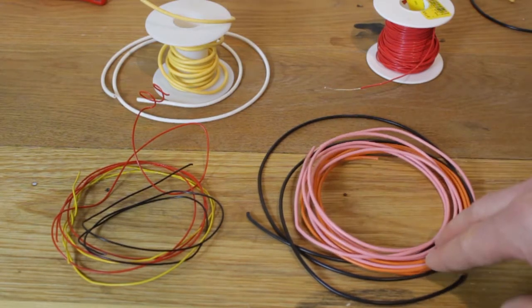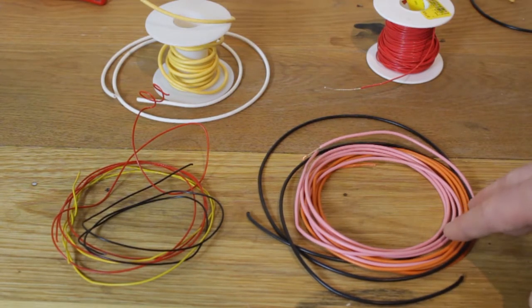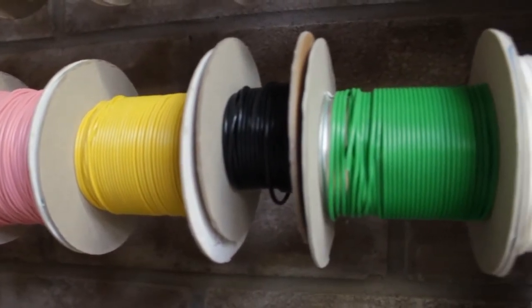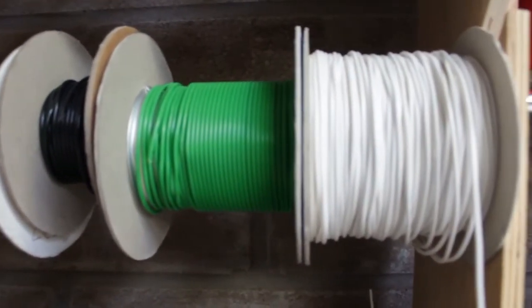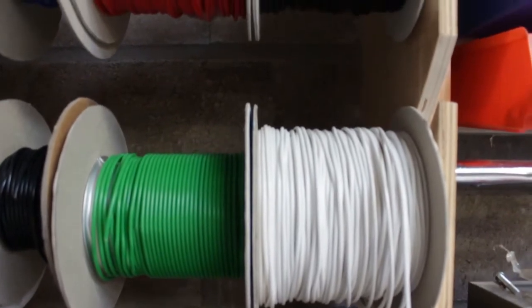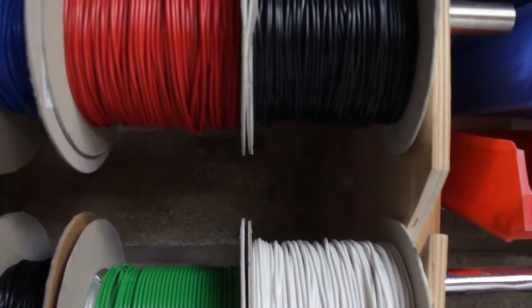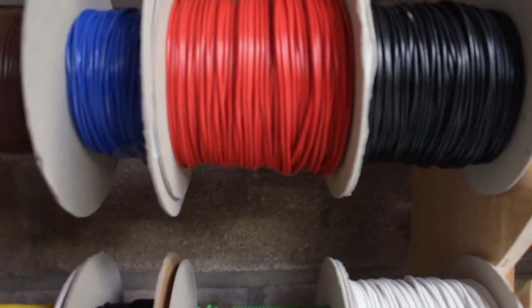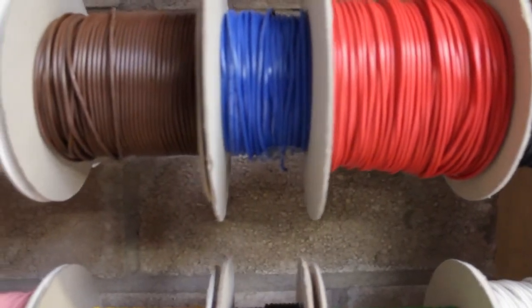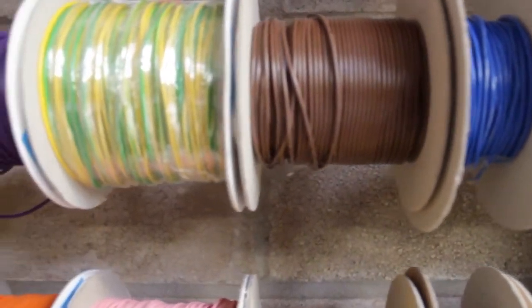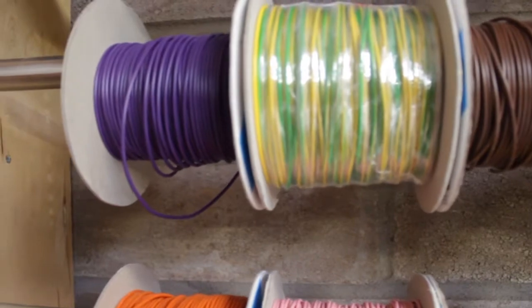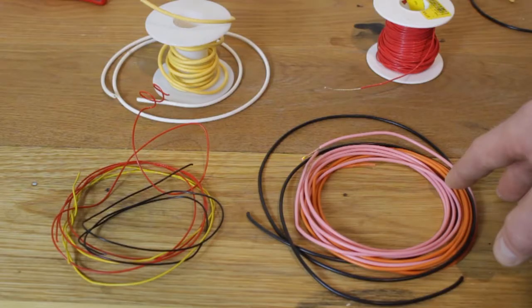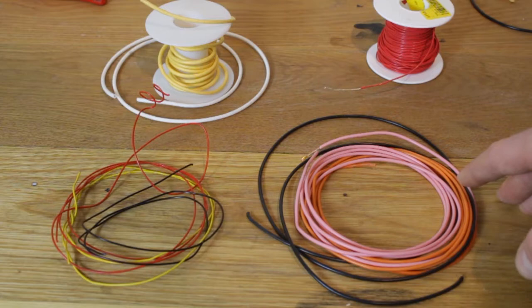What we've got here is tri-rated cable, and you can see the different colors. What the tri-rated part means is it meets three different standards: BS or British standards, UL or Underwriters, and CSA which is Canadian standards. That means it meets the North American and European wiring regulations.